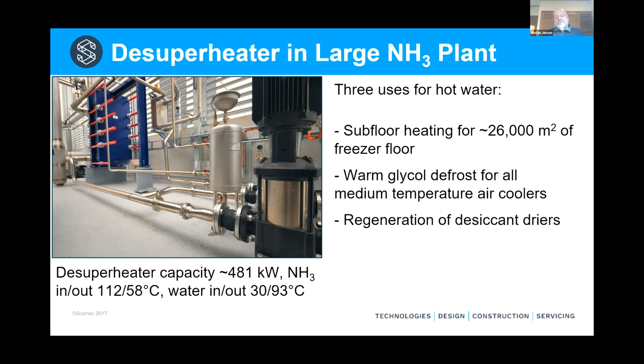Desiccant dryers are used in large freezer applications to prevent slippery floors. Slippery floors are dangerous. When people fall over, they lodge a workers' compensation claim, and that's what we're trying to avoid. So the regeneration of a desiccant dryer happens by pumping warm air of 60 to 70 degrees through a corner of the desiccant wheel to dry the moisture out. So the warm air is heated with the hot water that comes from the desuperheater.